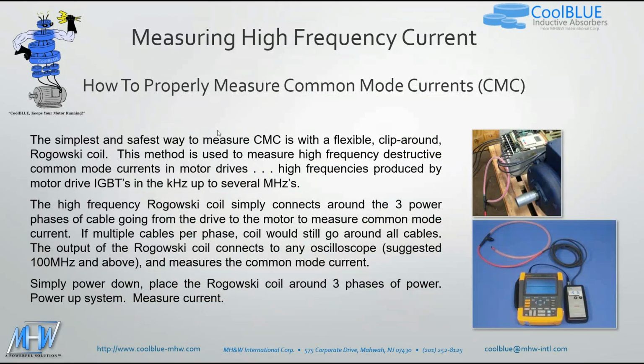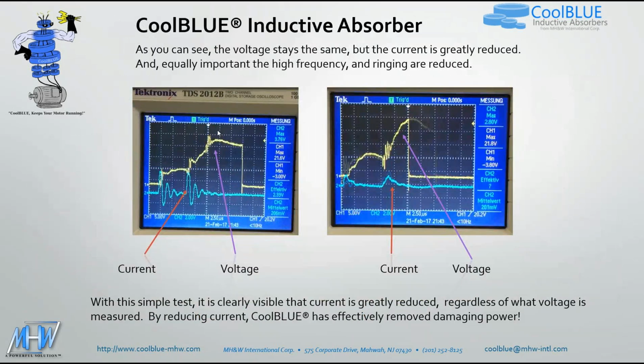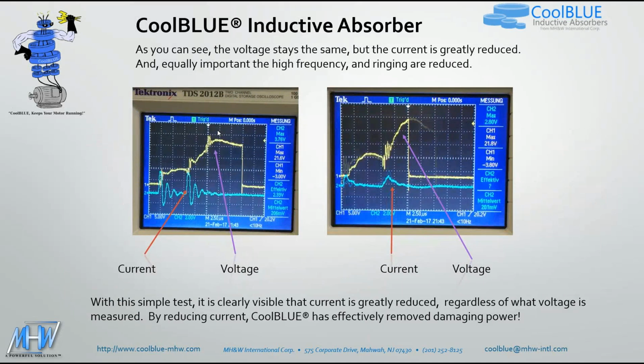So going on, let's see. Do you ever measure the shaft voltage directly with a probe on the shaft while you're checking with the Rogowski coil as well? It's possible, but it's generally not. It's more likely to be done in a lab environment, but out in the field, it's not preferred because of the safety hazards in getting into that part of the motor. It's generally not advised, and that's one of the big negatives.